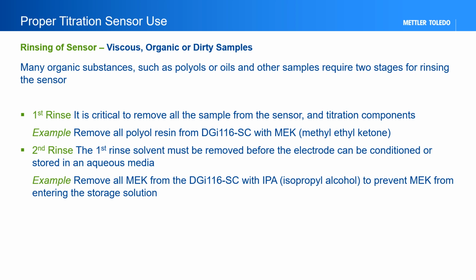Rinsing of viscous, organic, or dirty samples may require 2 rinse steps. Polyol titrations typically require 2 rinses. The first rinse, such as acetone or MEK, removes the polyol and solvent from the sensor. The second rinse, such as isopropyl alcohol, removes the first rinse and prepares the sensor for storage.